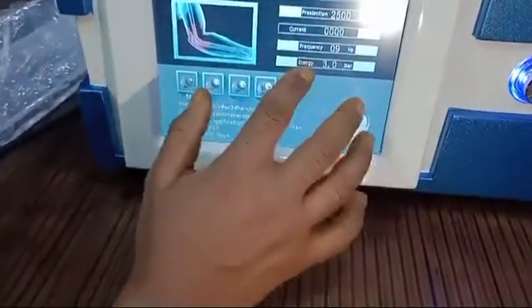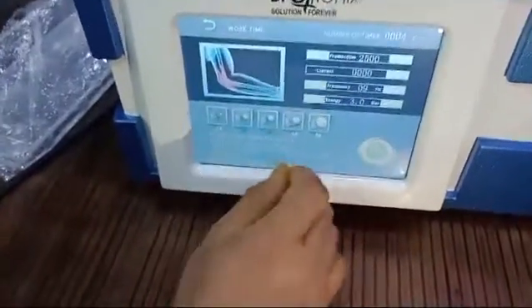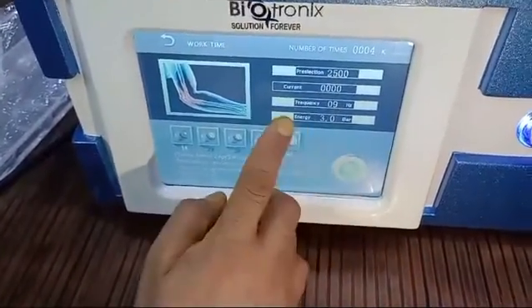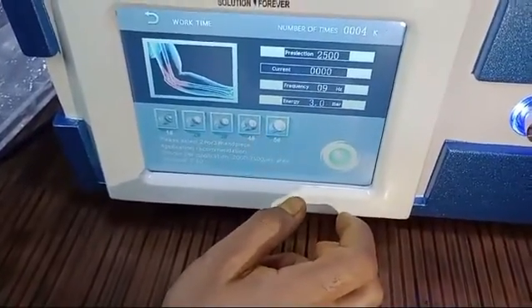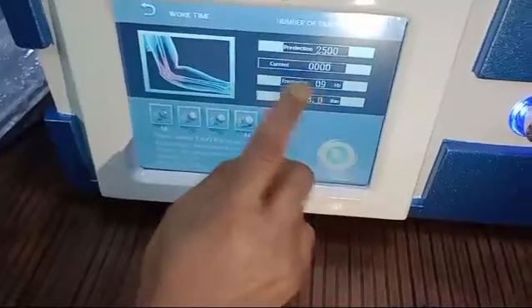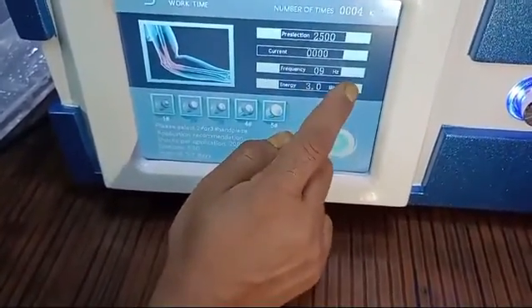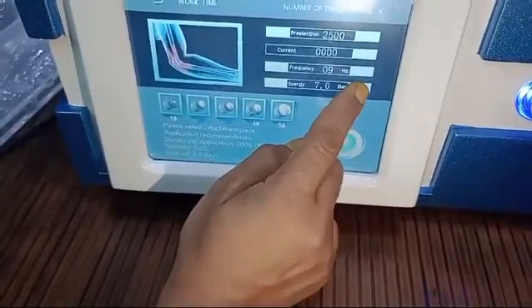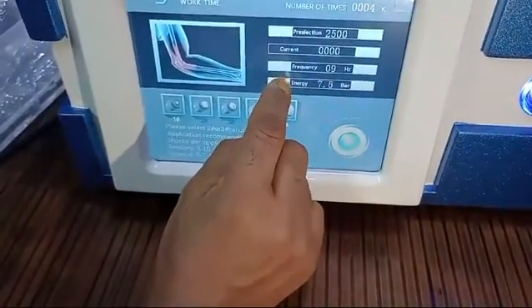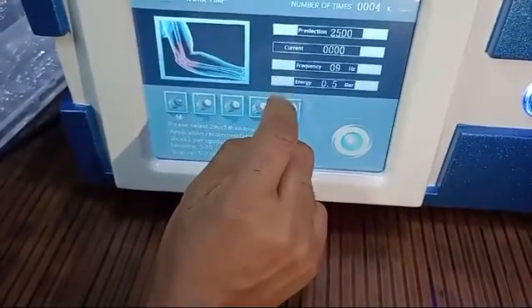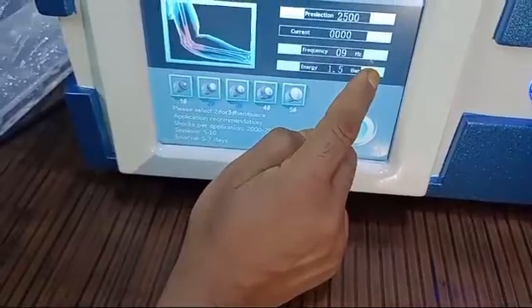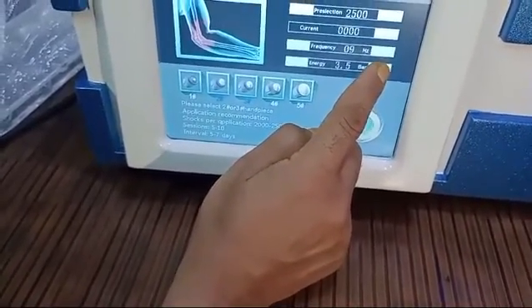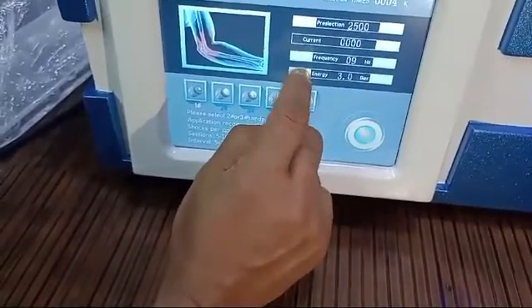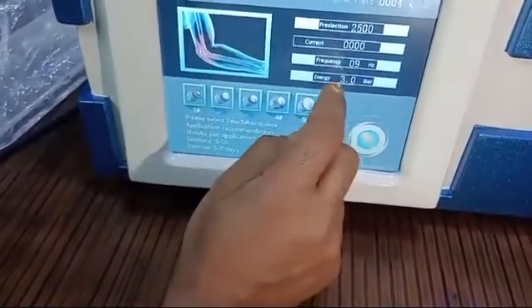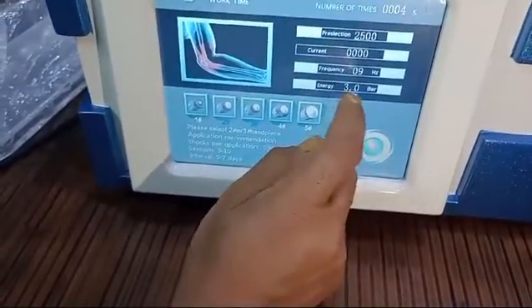You can see there is pre-selection of 2500, already all the parameters are fitted in the same. If you have to use the same for the treatment of elbow, you can start the same and use this parameter. But if you want to customize the treatment according to the doctor's need, you can adjust these parameters accordingly. This is 3 bar right now. You can increase or decrease the same up to 10 bar. You can see you can go up to 10 bar, and you can go minimum up to 0.5 bar. So 0.5, 1, 1.5, 2, 2.5, 3, 3.5, like you can go up to 10 bar. But previously in the program it was saved as 3 bar. So you can vary the same or you can select the same according to the frequency.